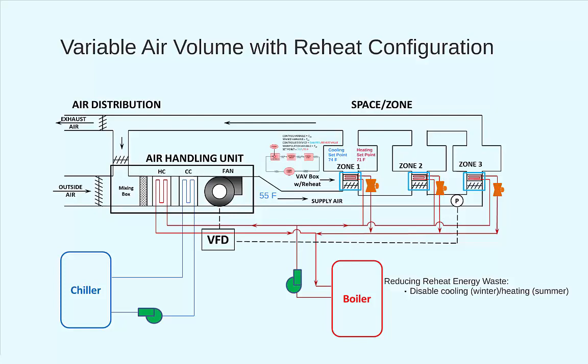One way to help out with this is to implement a supply air temperature reset schedule. This second approach can be done independently or in addition to draining chilled water piping.